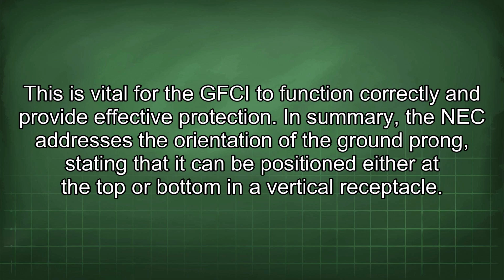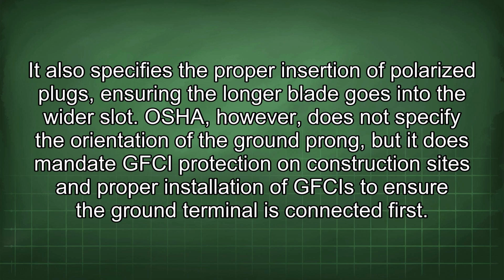In summary, the NEC addresses the orientation of the ground prong, stating that it can be positioned either at the top or bottom in a vertical receptacle. It also specifies the proper insertion of polarized plugs, ensuring the longer blade goes into the wider slot. OSHA, however, does not specify the orientation of the ground prong, but it does mandate GFCI protection on construction sites and proper installation of GFCIs to ensure the ground terminal is connected first.